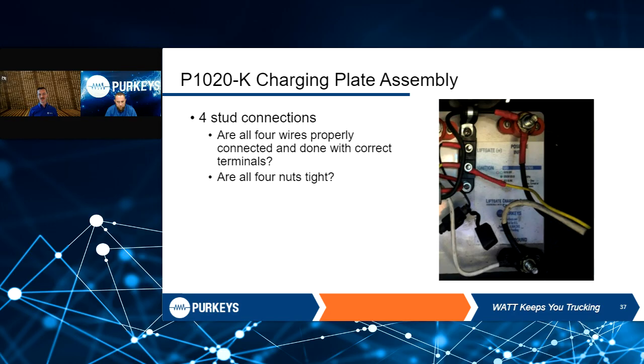I've seen it where that positive input stud was never tightened down at all. It was finger tight. You could loosen it by blowing on it. And eventually it ended up melting that stud completely out of the terminal block itself. Were it to short to something, of course, it is fused at 30 amps, so it wouldn't have caused anything major, but loose connections are a huge, huge thing to watch out for.